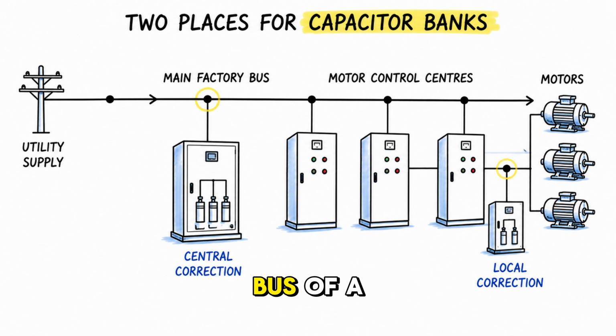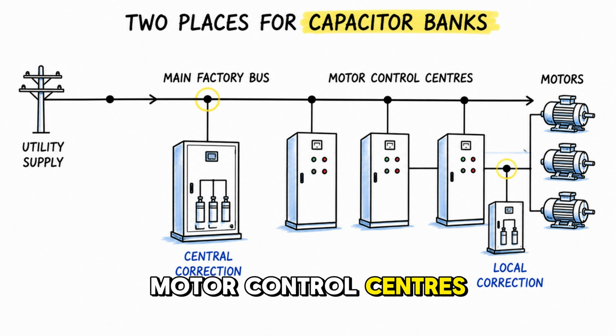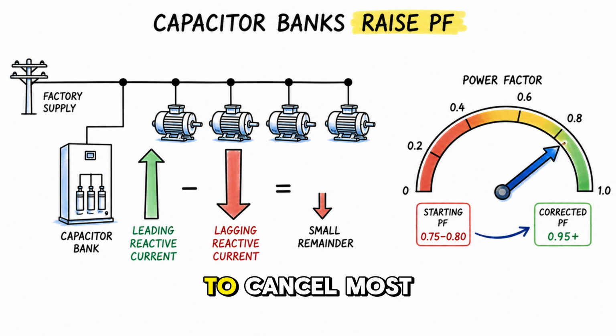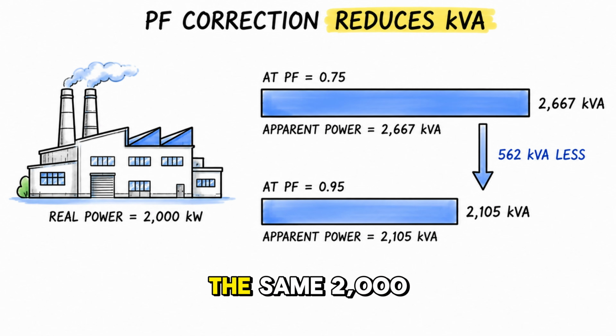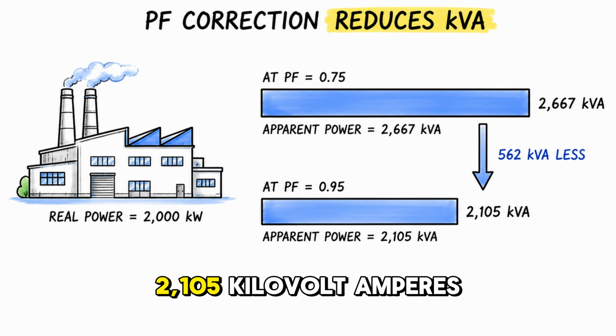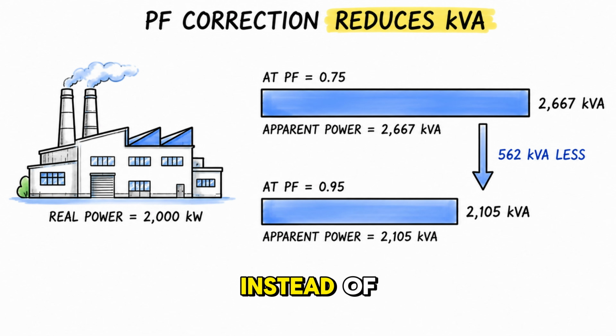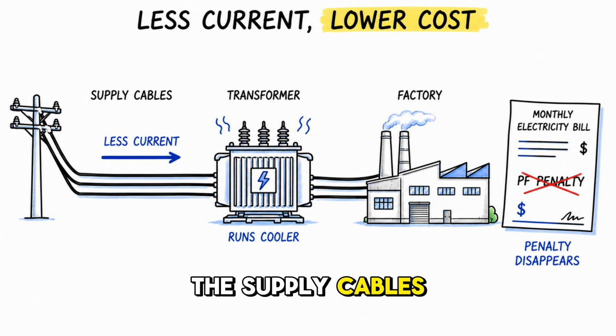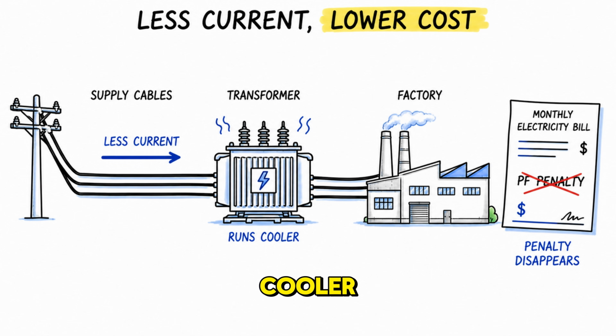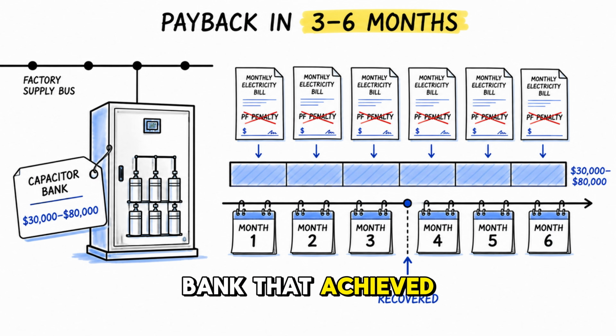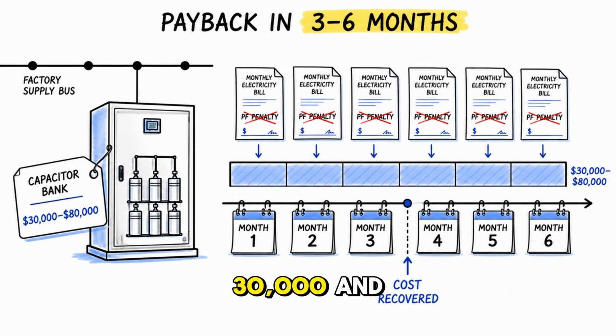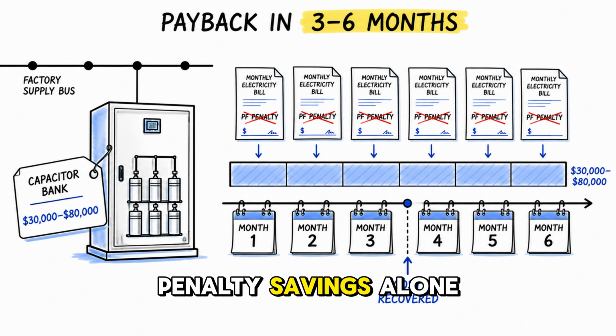Capacitor banks are installed at the supply bus of a factory or at individual motor control centers. They are sized to provide enough leading reactive current to cancel most of the lagging reactive current from the motors. The goal is typically to raise the power factor from 0.75 or 0.8 up to 0.95 or higher. At 0.95 power factor, the same 2000 kilowatt factory now draws only 2105 kilovolt amperes of apparent power instead of 2667. The supply cables carry less current. The transformer runs cooler. The penalty charge disappears. And the capacitor bank that achieved all of this typically costs between $30,000 and $80,000. For a facility of this size, a cost recovered within 3 to 6 months from penalty savings alone.